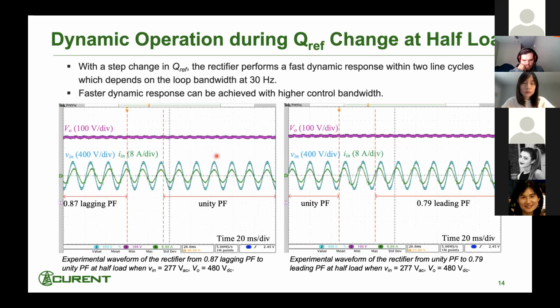We also tested the rectifier in dynamic operation at half load. Here we give a step change in the rectifier reference, and the rectifier performs a faster dynamic response within the 2-line cycle. This depends on the loop bandwidth of the rectifier loop at 30 Hertz. Well, if you want to achieve a faster dynamic response, you can further improve the control bandwidth.